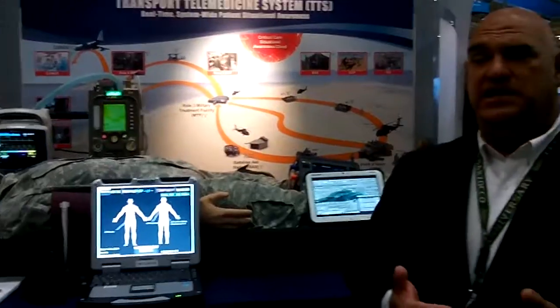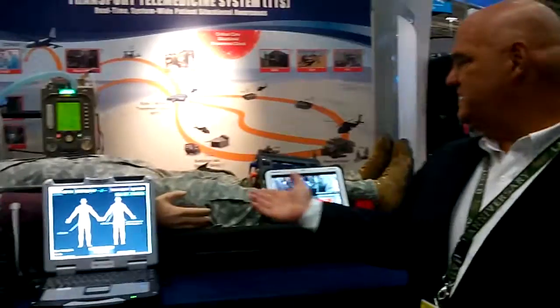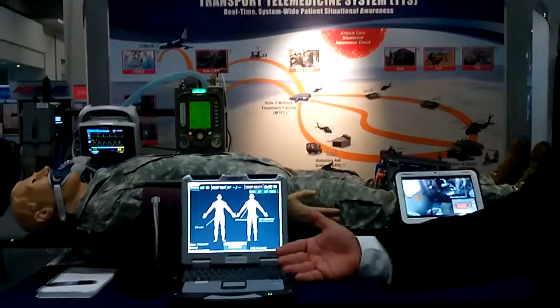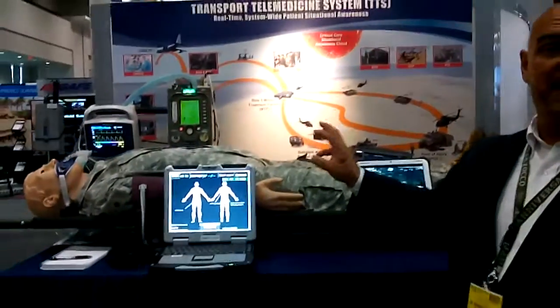One of the issues that we look at is our access point. Its purpose is to move medical and patient information. The FDA currently views that as what they call a medical data distribution system, an MDDS. The FDA does not see that as a type 2 regulatory device. But we expect that in the near future they will, because this data is intended to do real-time diagnostics by a remote physician. So we've implemented all of the processes and regulatory controls inside SNC to ensure that when we need to be FDA compliant or a type 2 regulated device, we'll be ready for that.